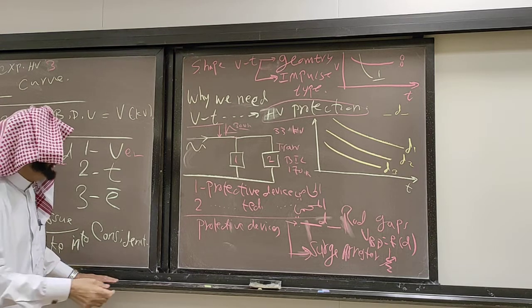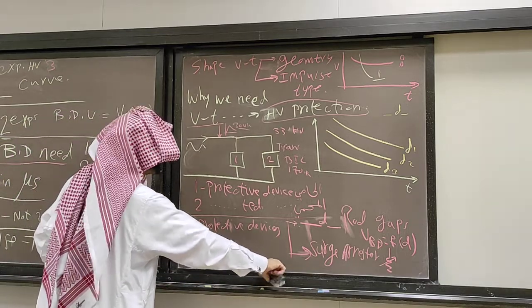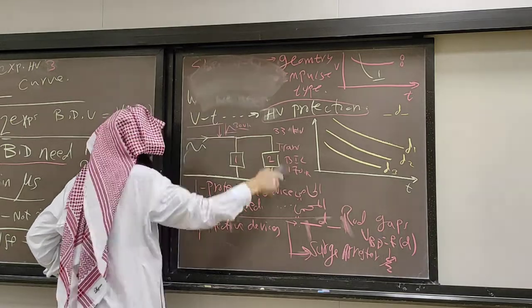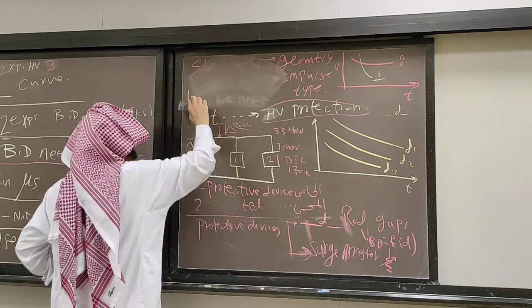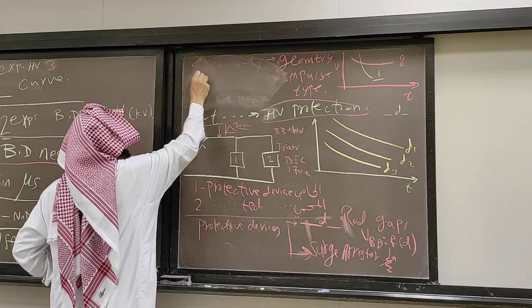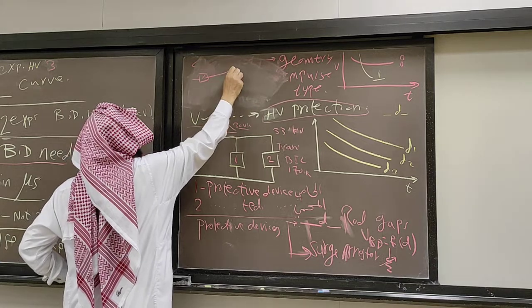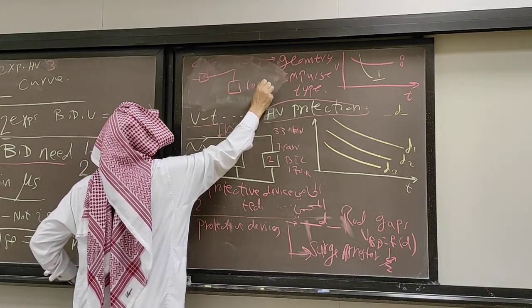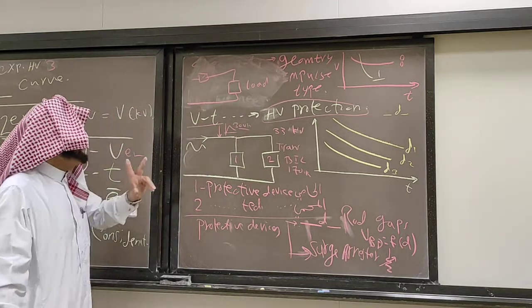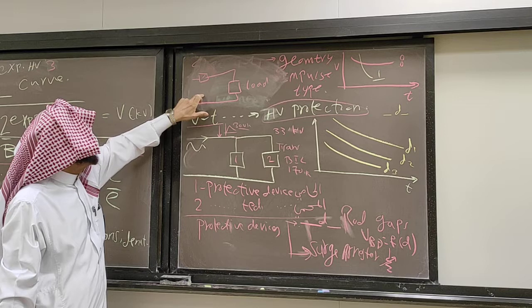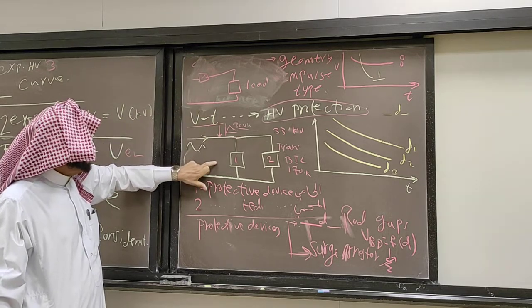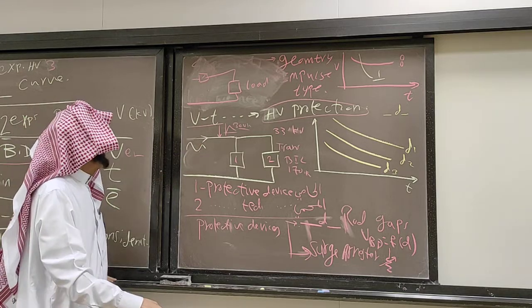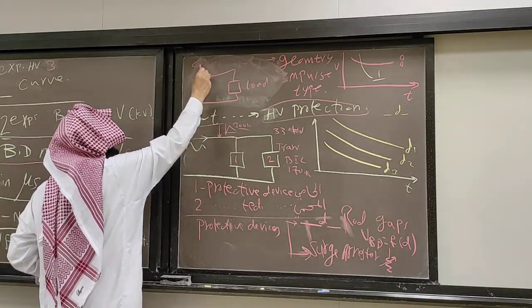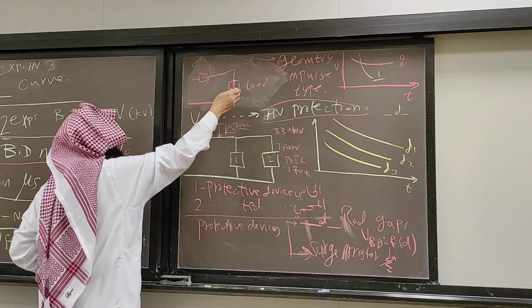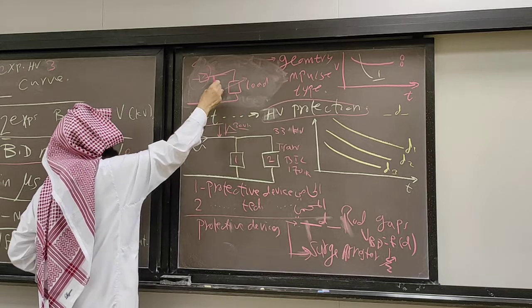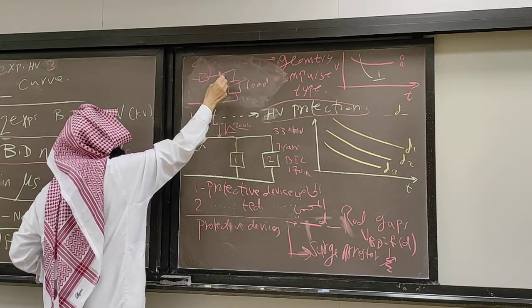Current protection: you have a circuit breaker or fuse, and this is your load. So there are two differences basically. The first difference is that this is a series connection, the protection in series, while here the protection is in parallel. And also, this device will not protect the load. This device will protect the wire. Because the load is variable, you don't know what the load is. But the wire, if the current is very high, it will be damaged. So you protect the wire.